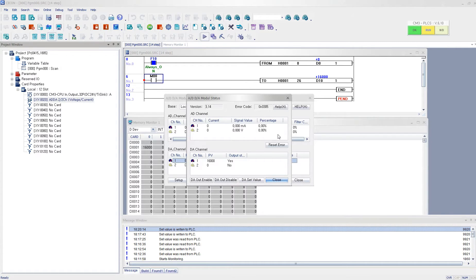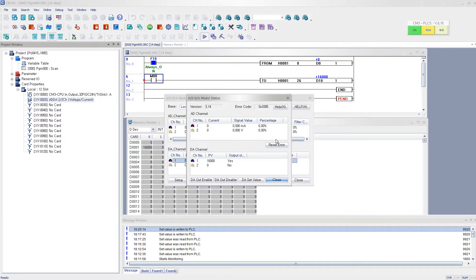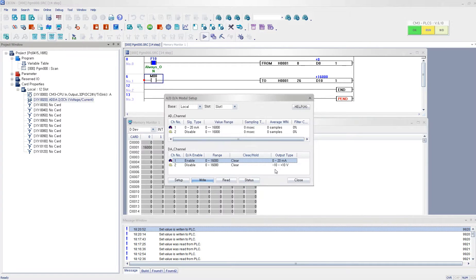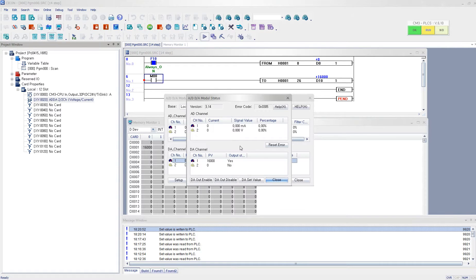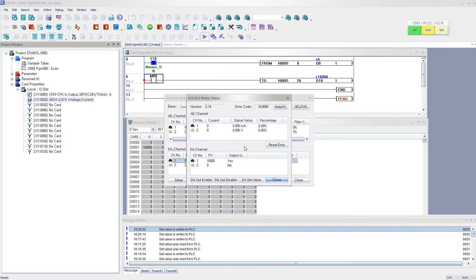Right now it is showing the error code because it is not wired with calibrator. And I am going to wire it right now. So I reset my error. I am going to current measurement, select okay.